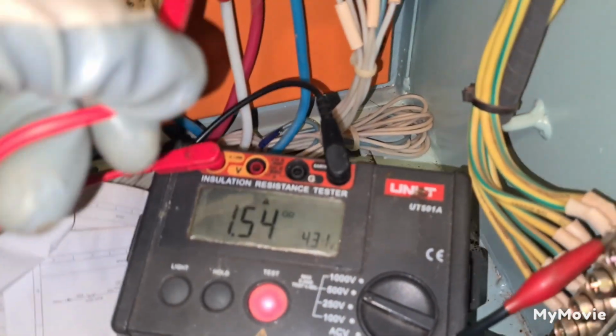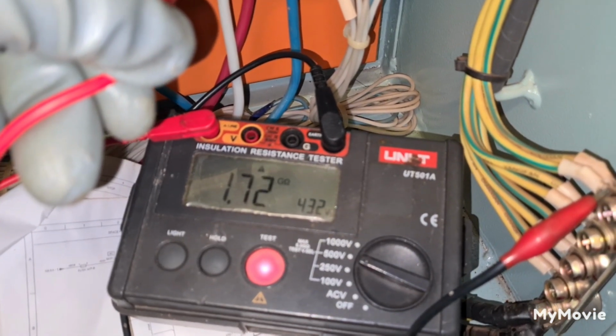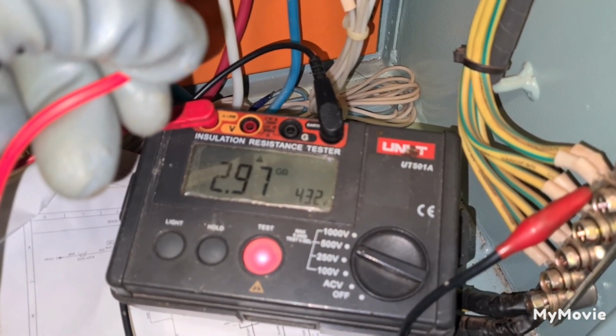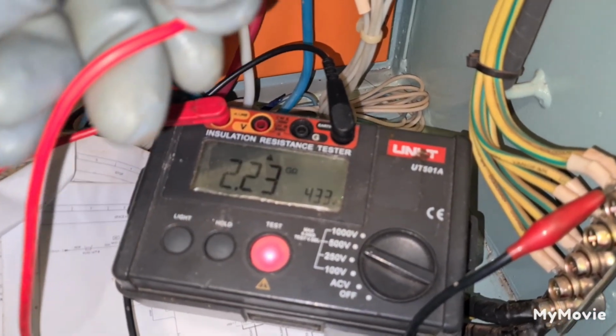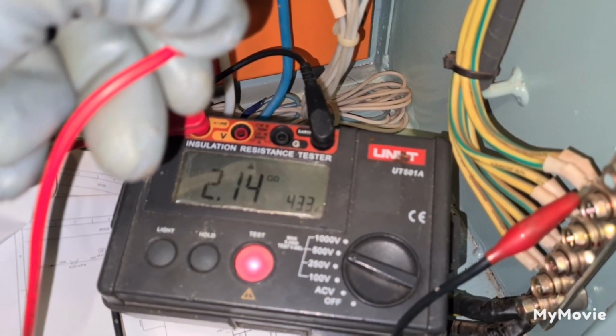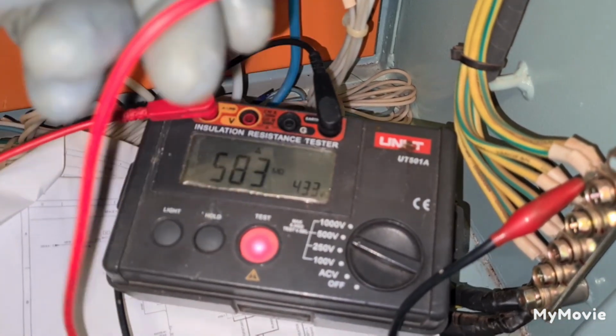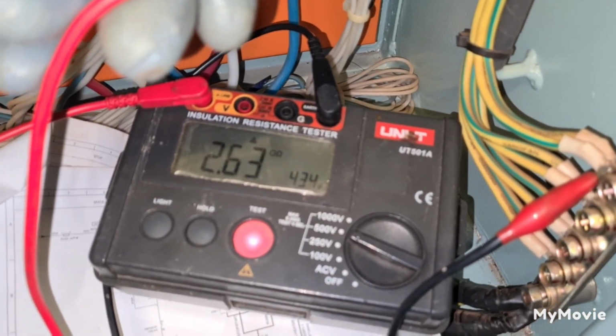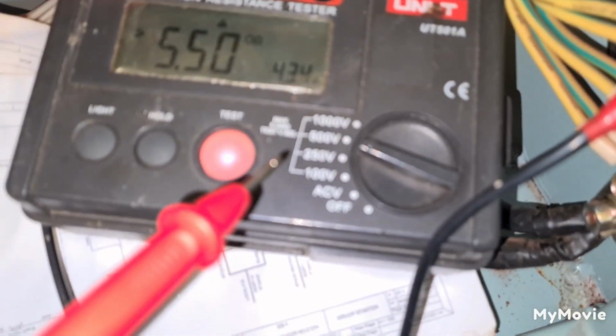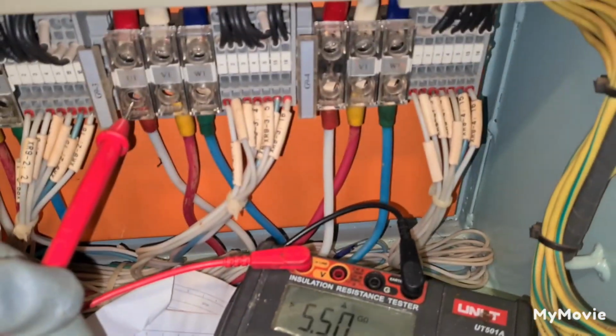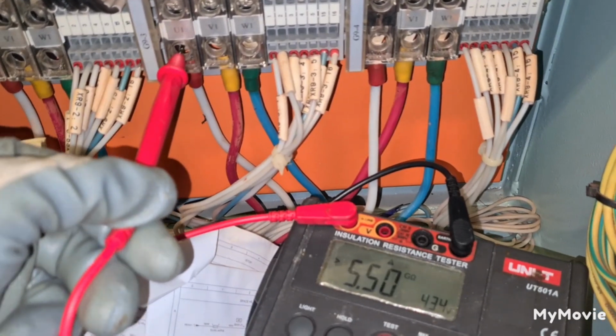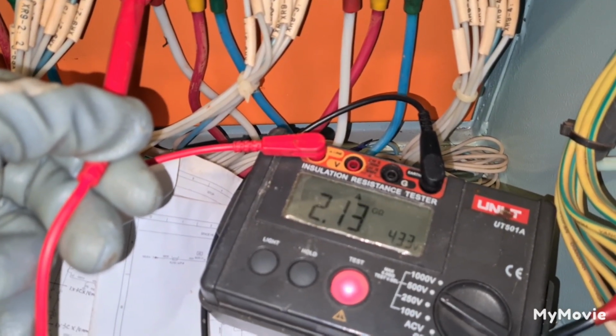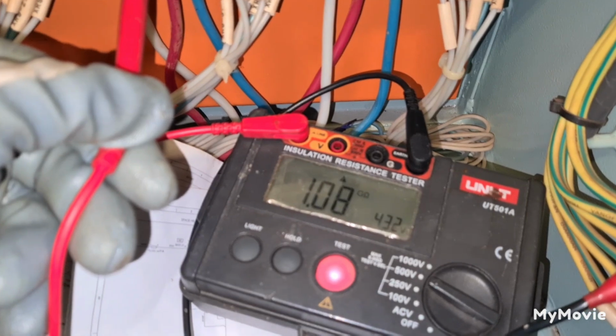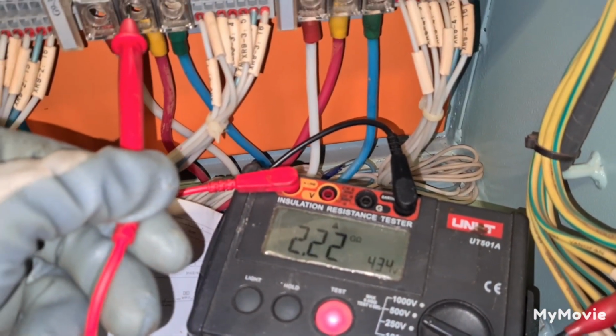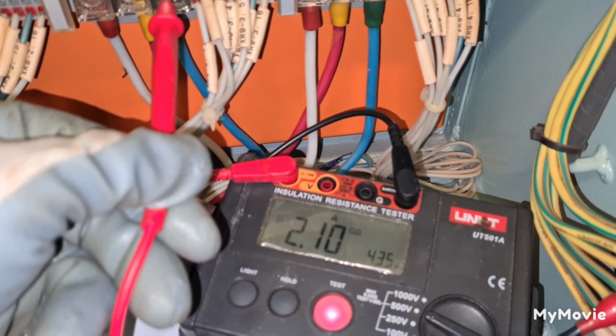this is having 1, 2, 3, 4, 5. 1.81 gigaohms with 432 volts. This one, line to ground, 2.16 gigaohms, and then this one, it has 2.81 gigaohms. That is the insulation value at 500 volt range. Also, on the other one, we have here 1, 2, 3, 1.84 gigaohms. Here, 1.55 gigaohms. And then here, 2.59. We can check also the other group of motors from here.